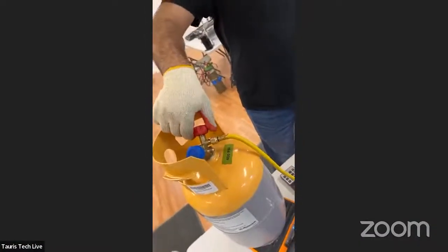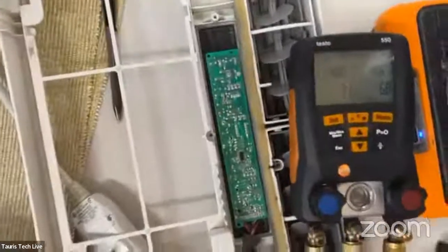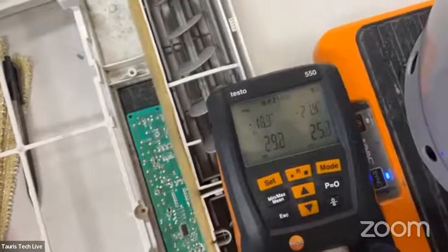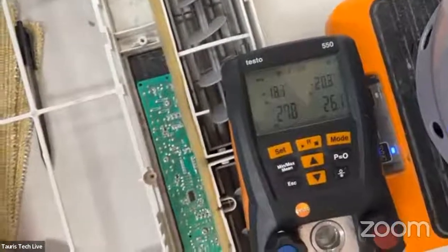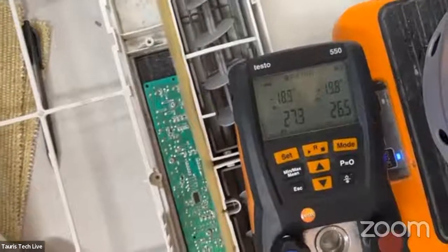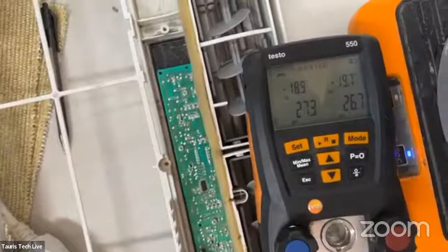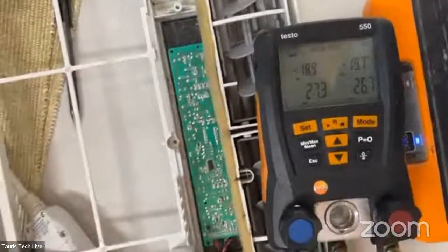So open up the liquid again. Just a little bit, close it. All I'm doing is putting a little liquid in the line. So open the blue valve again, and you'll see it. See that? That is liquid boiling. And you can see as the refrigerant gets sucked into the lower pressure, because we have a lower pressure in the machine, the vacuum is speeding up the charge. But the problem is eventually the pressure in the tank will be the same as the pressure inside the machine.